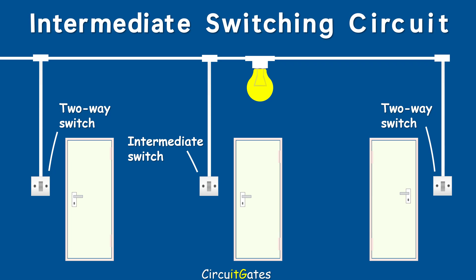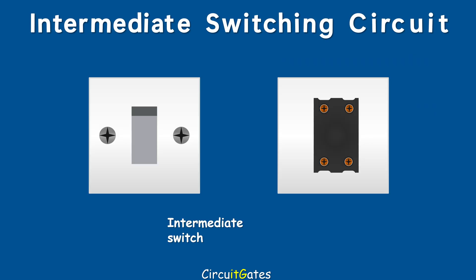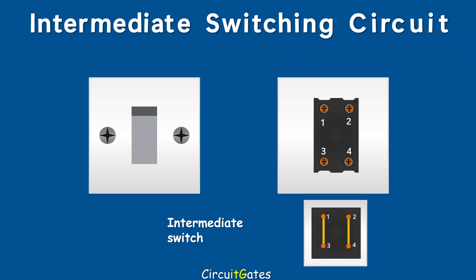An intermediate switch has four terminals, usually numbered 1 to 4. When the switch is operated, terminals 1 and 2 are connected to terminals 3 and 4 respectively, or terminals 1 and 2 are connected to terminals 4 and 3 respectively.